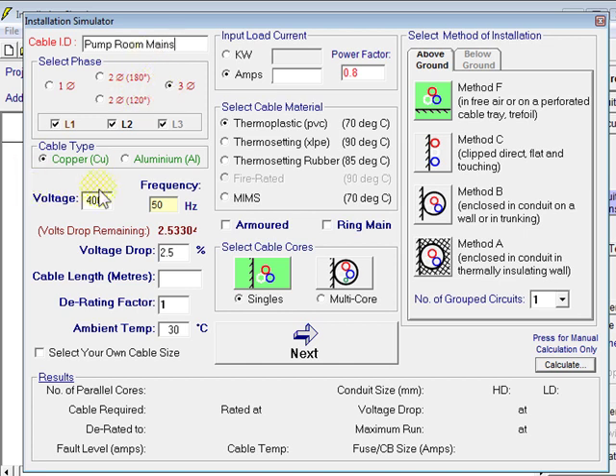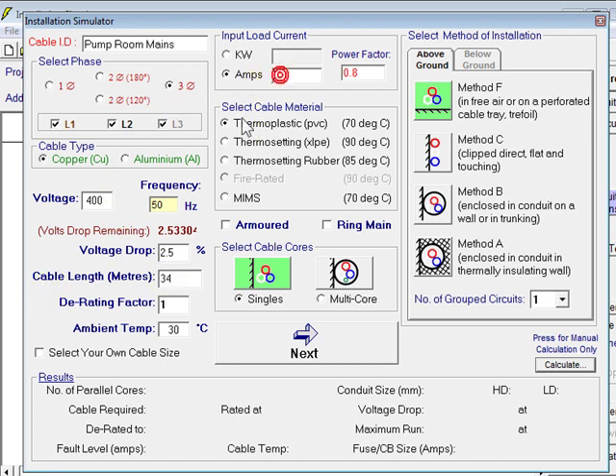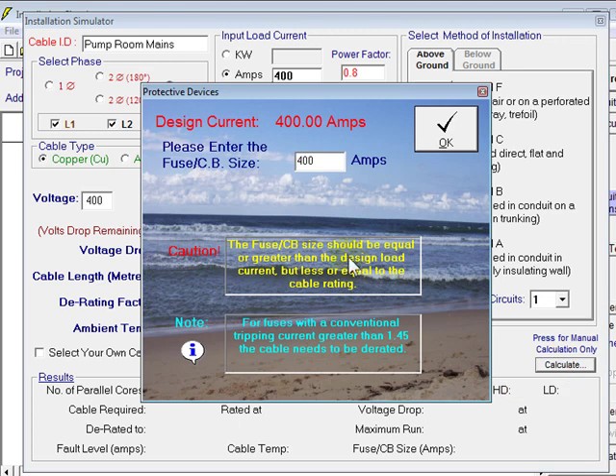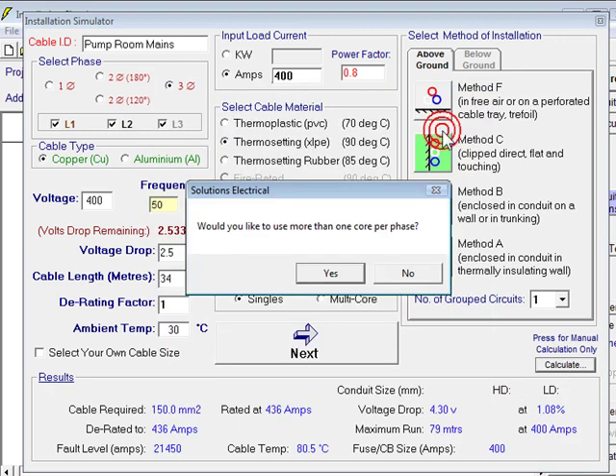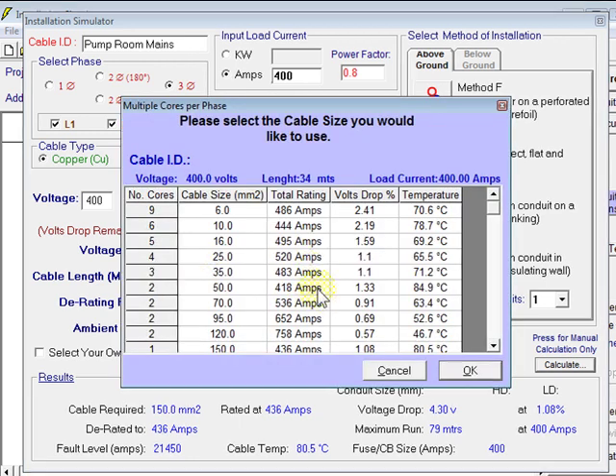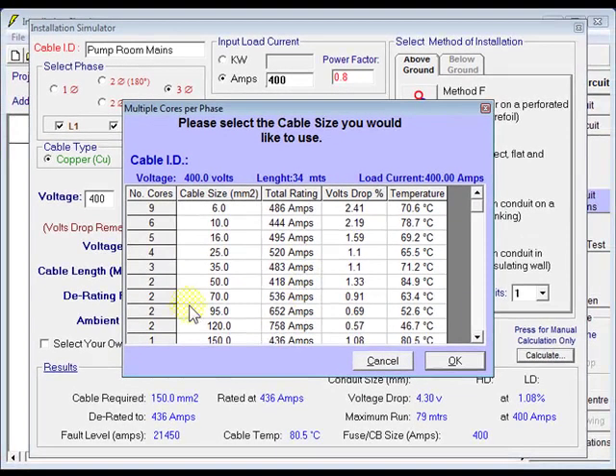It'll be three phase, 400 volts. Length of that run, 34 meters. The load on that run, 400 amps. XLPE 90, singles, clipped direct. So we go over here and calculate that. It's a 400 amp load, 400 amp breaker, click OK. Or if we would like to use more than one core per phase, we can click OK here.